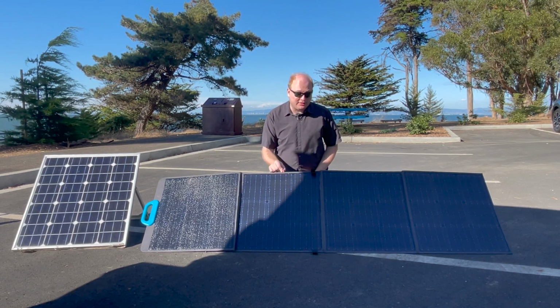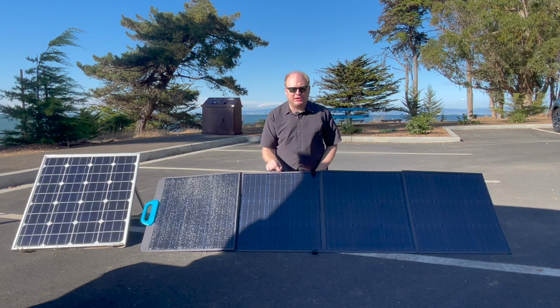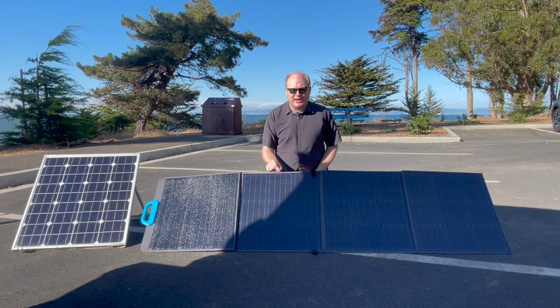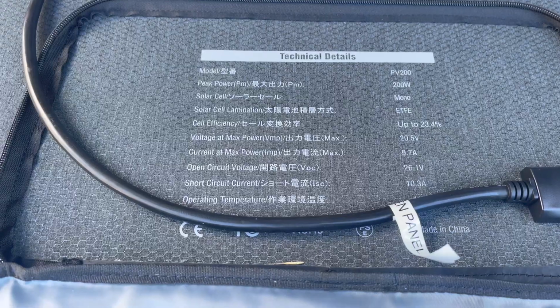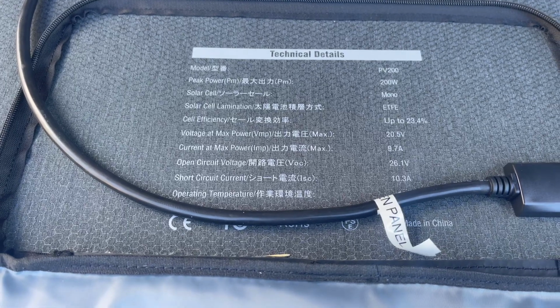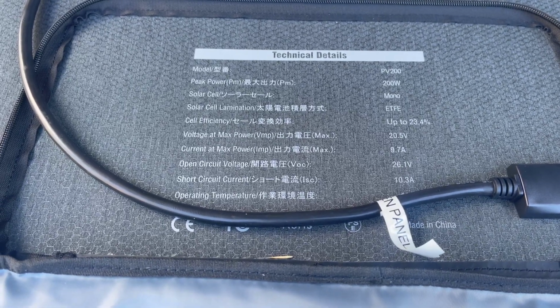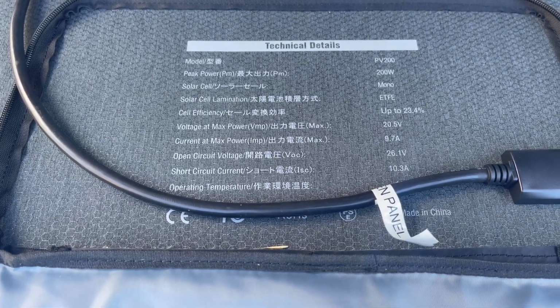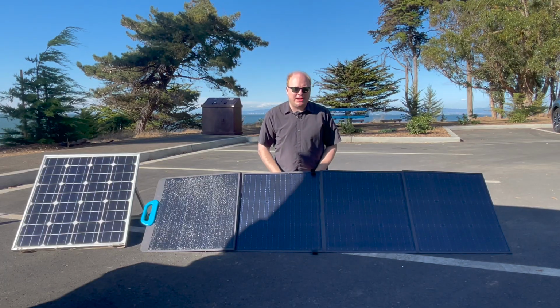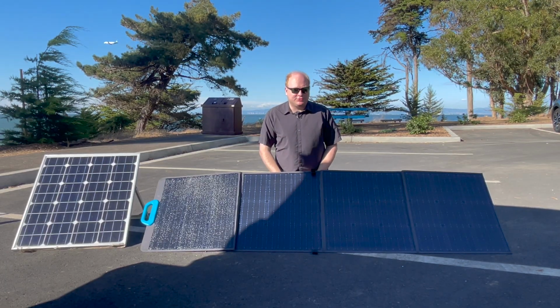In order to tell if the panel is compatible with your particular solar generator, you need to look at the specs on the panel, specifically the open circuit voltage. Line up that open circuit voltage with the open circuit voltage rating on the solar input. If the volts don't line up, even if the watts line up, it's not safe to use.